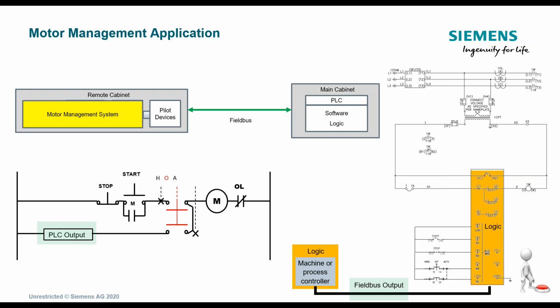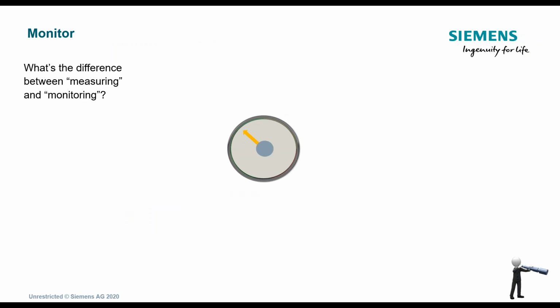Okay. So if you look down here, we're wiring in the stop-start circuit on the SIMOCODE, and we're wiring in the HOA locally to the SIMOCODE. The SIMOCODE has its own 24-volt power supply, so locally within the cabinet we can excite that stop-start switch and the HOA, so we don't need another power supply in the cabinet. And then we're going to remove, again, as I stated, those contactors, the overload contactor and that sealing circuit, or that interlock. That all goes away with the SIMOCODE because it's not required. So now we're reducing more wiring, reducing mechanical failures as contacts, because we're getting rid of 2 of those.